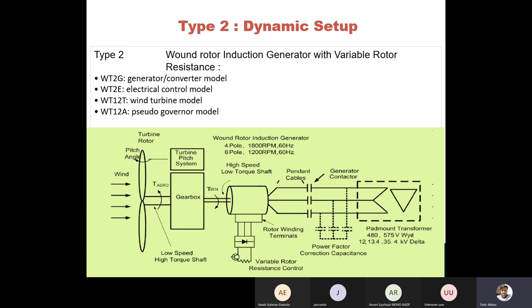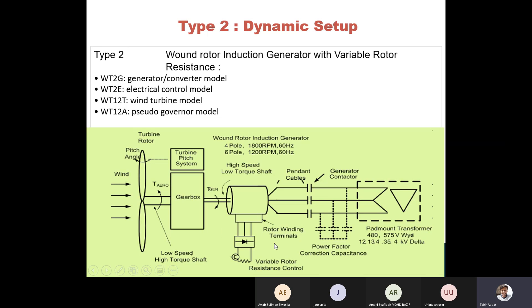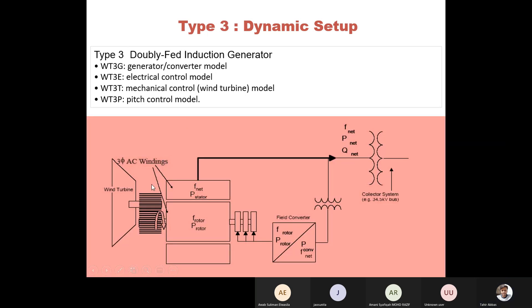Type 2 is the wound-rotor induction generator with variable rotor resistance, which adds one control — a variable rotor resistance control. You can control the machine's rotor winding terminals through this variable rotor resistance control to adjust speed and voltage behavior. An additional dynamic model involved here is the electrical control model, so for Type 2 there is the generator/converter model, plus the electrical control model.